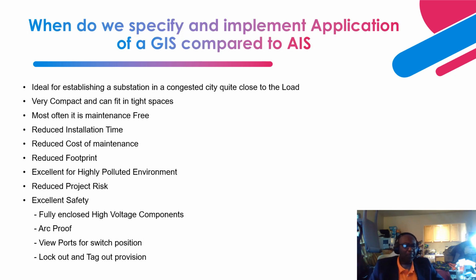Next, let's talk about what a gas insulated switchgear is and when we specify or implement its application. A gas insulated switchgear basically comes in the form of metal enclosed switchgear, compartmentalized and modularized, filled with high pressure SF6 gas. Compared to AIS, the insulating medium filled in the GIS has a high dielectric capability compared to an air insulated switchgear.